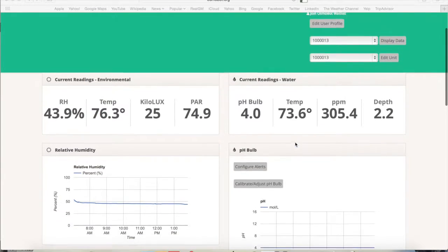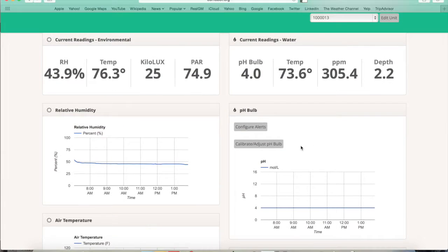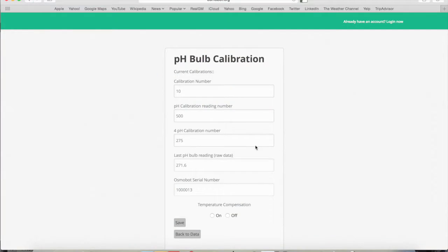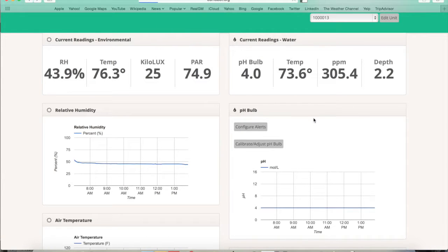We're going to need to scroll down and click Calibrate/Adjust pH. Here at the bottom of the screen we can see our latest raw data reading. It's a little bit lower than our current calibration, so we'll take that raw data reading and enter it under the 4 pH calibration number, make sure temperature compensation is off, and hit save. Now we're back to our main page, and we can actually see that the calibration has taken effect.